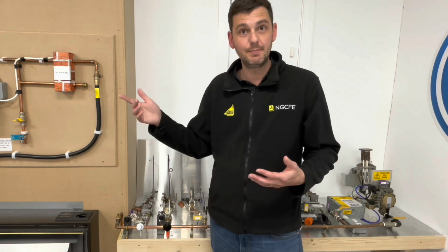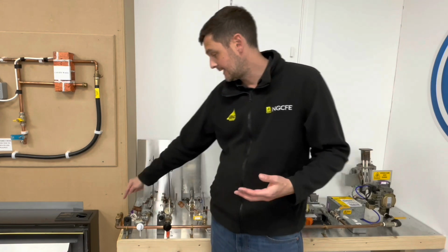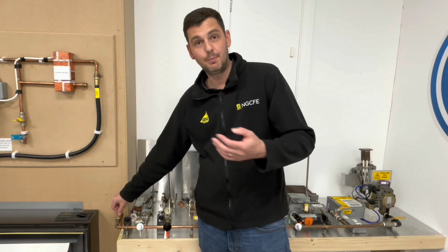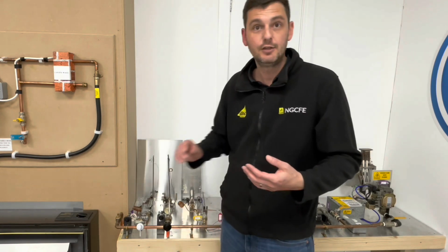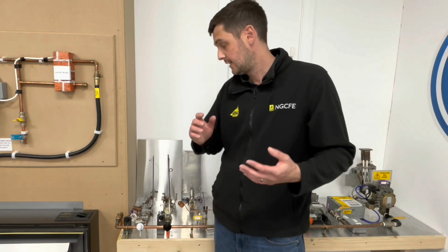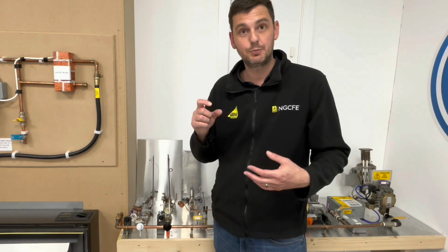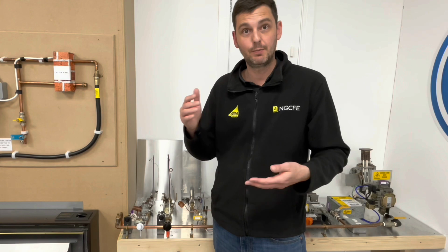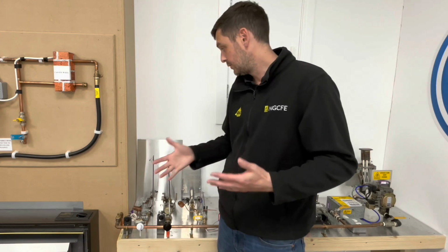So you can do that via the meter, or you can do it if there's a test point on the appliance side of an isolator. You can do it there too. And all you're doing is you just take the gas pressure, close the valve so that it's not being replenished. And if the valve was passing still, you would see a drop on a manometer. So there we go, that's your liquid expansion thermostat with thermoelectric valve.